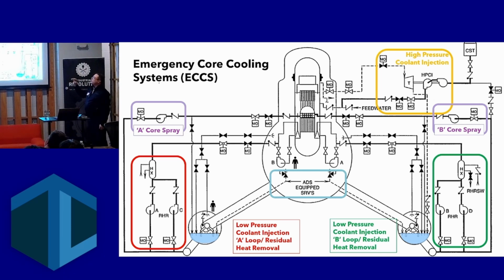Then we have core spray pumps. Here we show 2 core spray pumps, though Peach Bottom actually has 4 core spray pumps. And these, as the name implies, spray the core. You can see the injection line from the pumps goes inside the shroud, and there are 2 rings encircling the fuel right at the top, meant to spray down into the fuel as a last ditch effort, we'll say, to remove a significant amount of heat. As you remember, atomized water, liquid water droplets, flash to steam very quickly, but they'll also remove a lot of heat very rapidly.